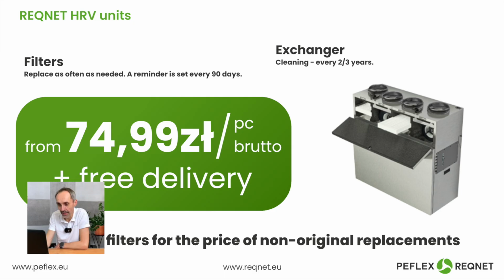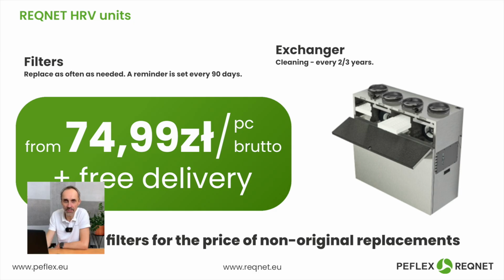As for replacing filters, change them as often as necessary. In my opinion, that's the most honest answer, because depending on the amount of air flowing through and the location of the buildings, these filters can get dirty faster or slower. That's why there's a time-based reminder every 90 days, during which we recommend simply checking the ventilation unit to see if the filters are already dirty, or if they can possibly stay in for another period, right? As for the heat exchanger, manufacturers recommend cleaning it every 2 or 3 years.